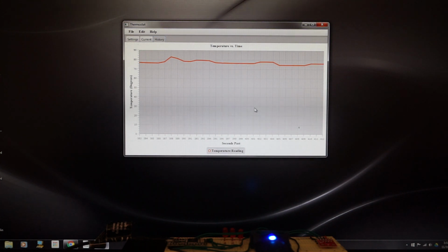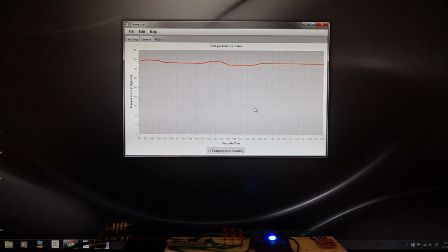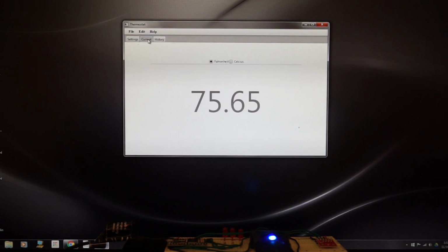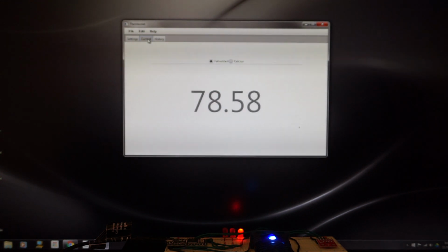One thing that you will notice is the LEDs are off, and that's because of the way it's implemented right now: it only changes on an event where the high threshold or low threshold boundaries change. Originally we had 80, so if we can get the temperature back up to 80, it should activate the alarm and start operating as normal once again. And there we go.